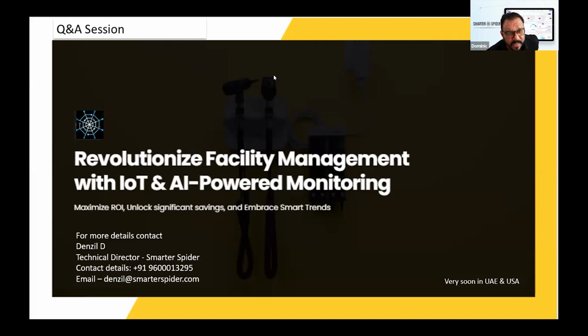Since I'm part of the National Building Code, I will answer that. We are recommending it at a state level. Fire is a state subject, it is not ruled by NFPA alone. NFPA is just one of the standards; we have IS and BS standards in India too. The Maharashtra government is making it mandatory, Telangana government is making use of IoT mandatory for fire protection systems, not necessarily just the fire alarm system, but when they say fire system, it covers fire detection, firefighting, everything. So a lot of government gazettes are being released. Karnataka is also in the process, and Tamil Nadu is advising all developers to implement IoT. Once that's done, all that's required is to take input from your panel and integrate it with IoT.